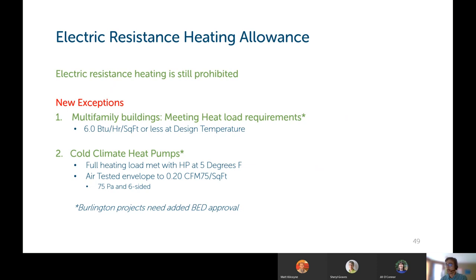For cold climate heat pumps, as I mentioned in the definition earlier of what that is, full heating load must be met by the heat pump at 5 degrees Fahrenheit. The envelope must be air tested to an even lower number of 0.2 CFM per square foot at 75 pascals. The normal code value for the 2020 code is 0.3, so it's a bit tighter. Again, that's 75 pascals and six-sided. There's a little asterisk here for these two. If these projects are in Burlington, Burlington Electric Department needs to approve these projects before they can be using electric resistance backup heating.